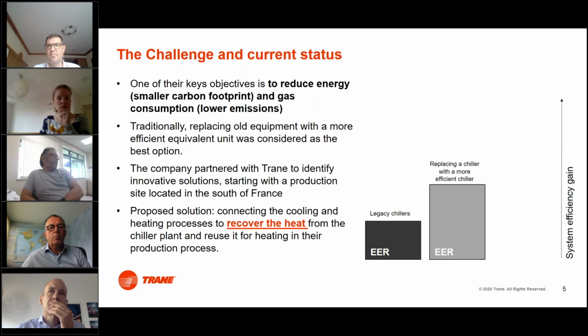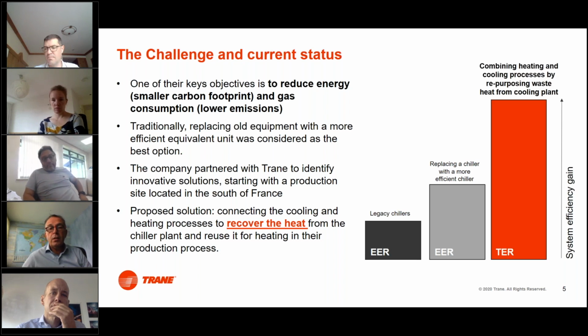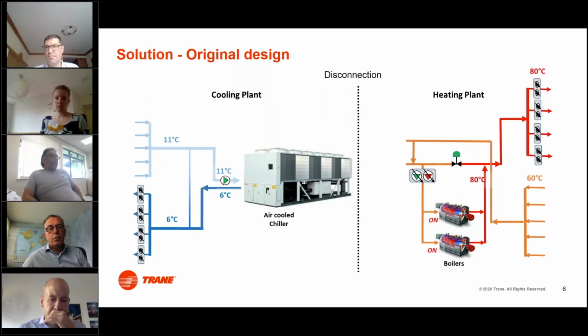So there's a huge gain already to be achieved when you replace an old existing chiller unit with a new chiller unit. But during that discussion, we also started discussing and discovering the potential to connect the dots of the heating and the cooling. At the end, when we could identify the heating and cooling opportunities in that process, we could see that the energy gain would be much higher than just the doubling of efficiency by the cooling plant itself.